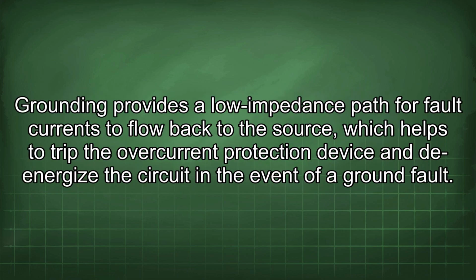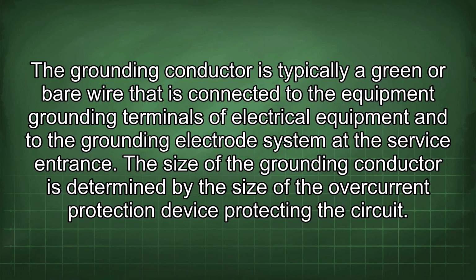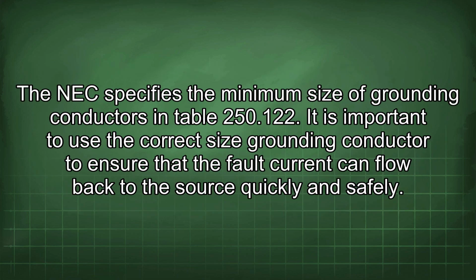Grounding provides a low impedance path for fault currents to flow back to the source, which helps to trip the overcurrent protection device and de-energize the circuit in the event of a ground fault. The grounding conductor is typically a green or bare wire that is connected to the equipment grounding terminals of electrical equipment and to the grounding electrode system at the service entrance. The size of the grounding conductor is determined by the size of the overcurrent protection device protecting the circuit. The NEC specifies the minimum size of grounding conductors in Table 250.122. It is important to use the correct size grounding conductor to ensure that the fault current can flow back to the source quickly and safely.